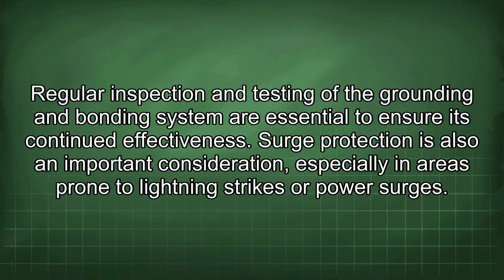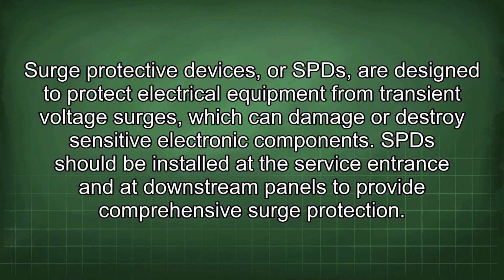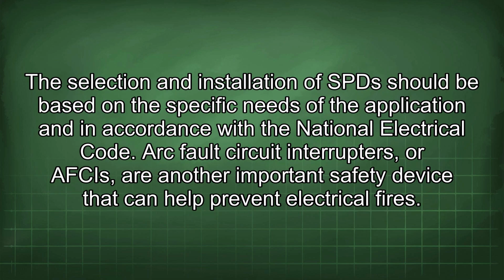Surge protection is also an important consideration, especially in areas prone to lightning strikes or power surges. Surge protective devices, or SPDs, are designed to protect electrical equipment from transient voltage surges, which can damage or destroy sensitive electronic components. SPDs should be installed at the service entrance and at downstream panels to provide comprehensive surge protection. The selection and installation of SPDs should be based on the specific needs of the application and in accordance with the National Electrical Code.